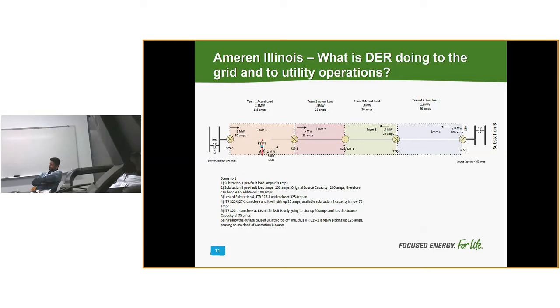So 325-1 now wants to close so we can pick up this section. I've lost the source, so I just want to pick up this section here. It wants to close to pick up 50 amps, right? The source here can handle 75 amps, so we're good to go. It will close. In reality, that is not the case.